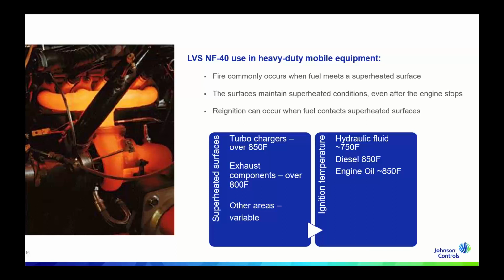The concept here was that dry chem would give rapid flame knockdown, and the liquid would provide the cooling capabilities to minimize the reflash that we talked about when you have superheated surfaces that are running above the auto ignition temperature of the different fuel sources. The surfaces can exceed the temperature of auto ignition, and then the contact of that fuel source with the superheated surface could cause combustion. The design intent of the liquid and the liquid-only system is still to reduce the surface temperature of the surfaces so that they are below the auto ignition temperature of the fuel.